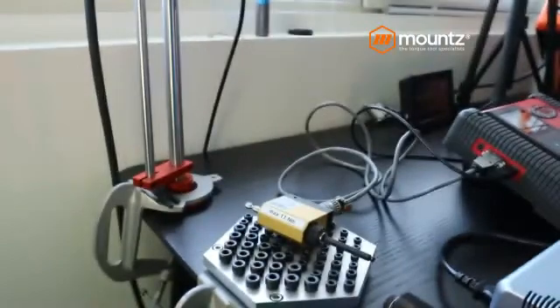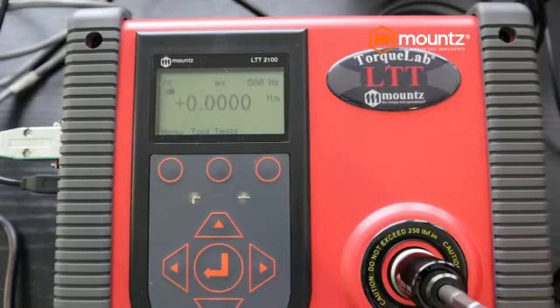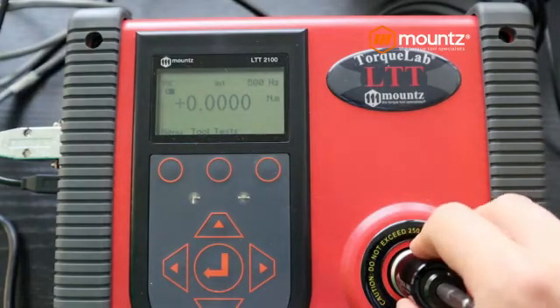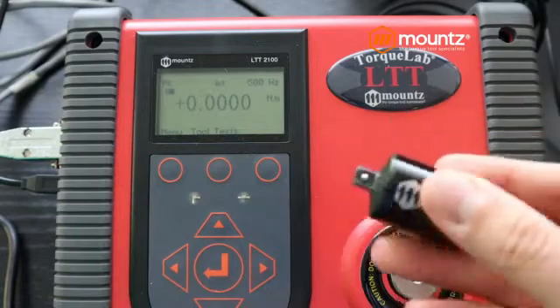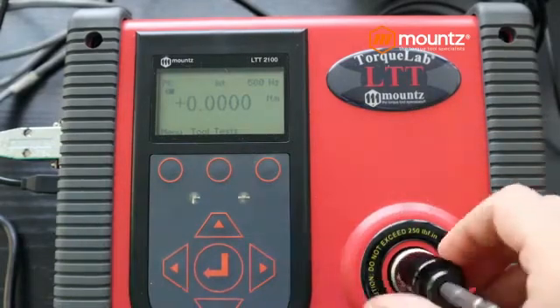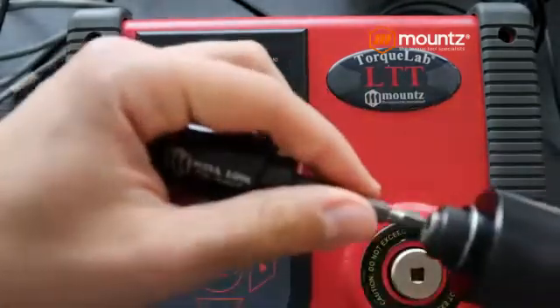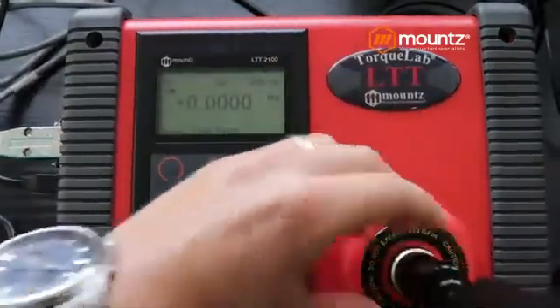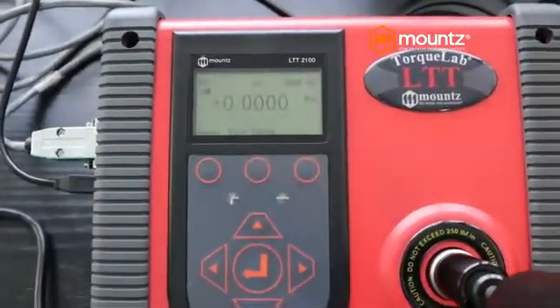Looking at the LTT, I want to start by showing the difference between static and dynamic measurement values. To do that, I'm going to use the HF 100 electric screwdriver onto the static sensor, making sure to use the proper accessories: a round down adapter with the proper bit, mounted in the bit holder. Then we can go ahead and make some measurements.